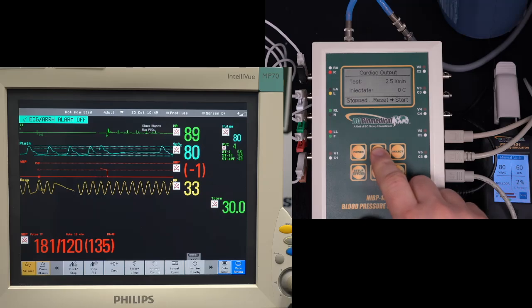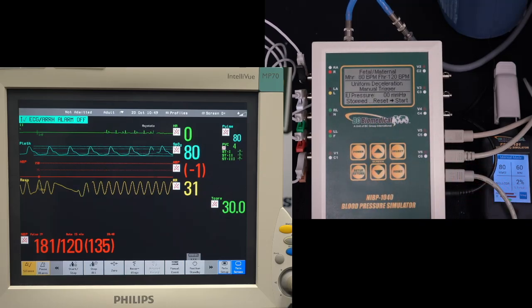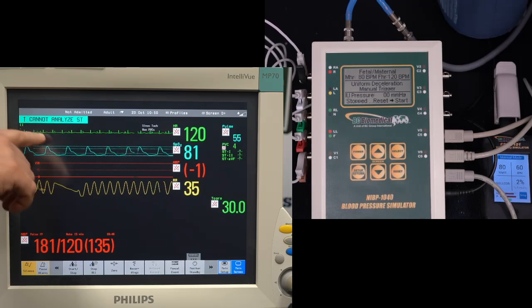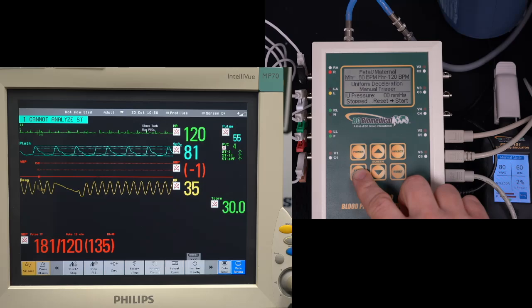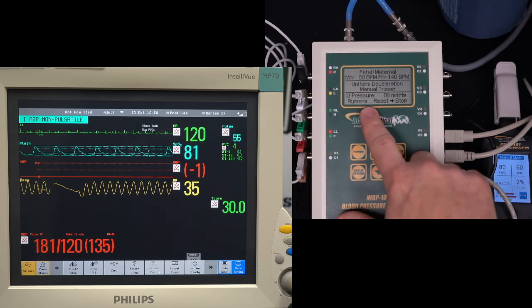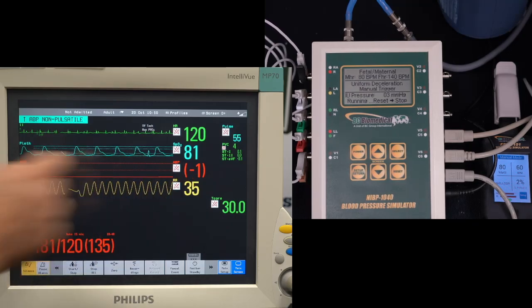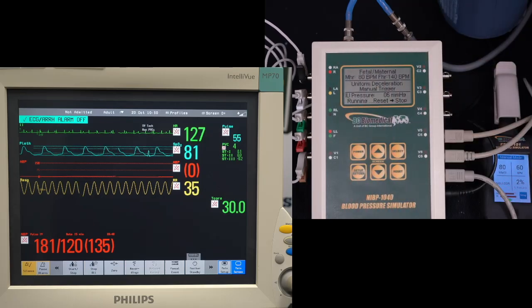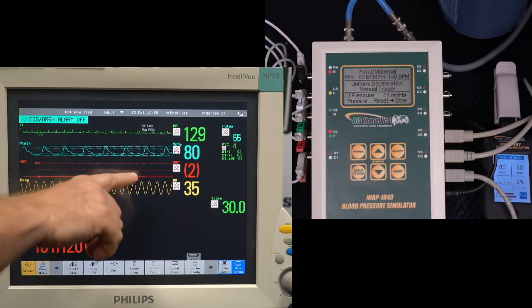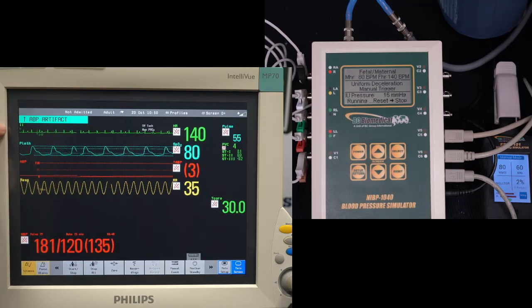So the important thing, the fetal maternal mode, it's not for testing. You know, it won't do a TOCO simulation, but what it does is it will simulate the IUP pressure. So we can do that on the IBP channel, and we get a superposition of the fetal and the maternal heart rates in the ECG. So when I run that, now it shows that it's running, and we'll see the IBP pressure change as that contraction runs through the timing. Yeah, so the pressure will start to change, and then if we could separate the fetal and the maternal heart rate, we would see the heart rate change too.